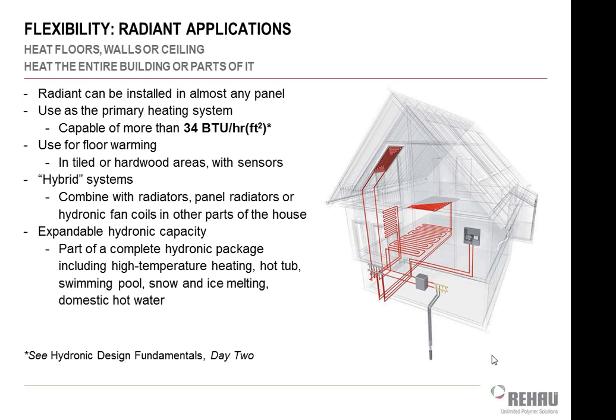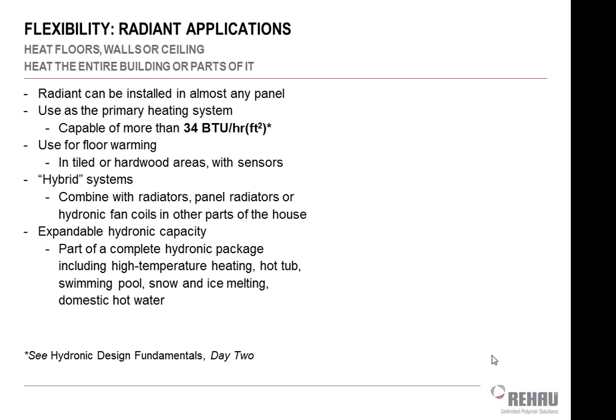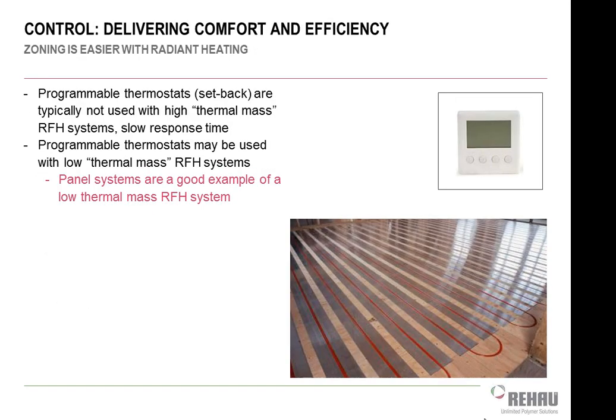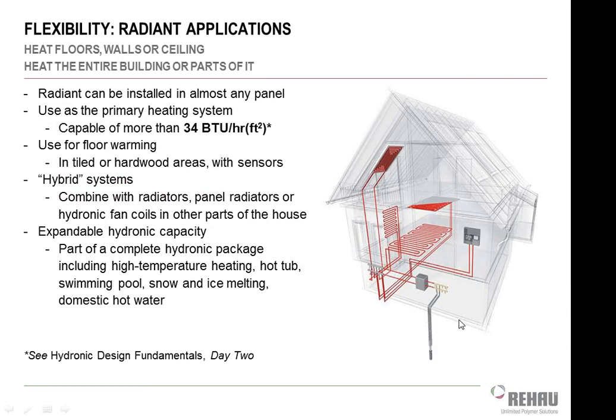Those work best when you get the tubing very close to the floor surface area. You don't want to have 3-4 layers of wood in between there, or carpeting or something like that that's going to act as an insulator. So those staple-up systems really only work for floor tempering of tile or wood floor areas. So we do those often in bathrooms or in kitchens. If you really want to heat your house with it, you need to put it in the concrete, or you need to rip up your floor in your kitchen and those other areas and put in some kind of paneling system like this one here that'll spread out the heat with those aluminum panels.